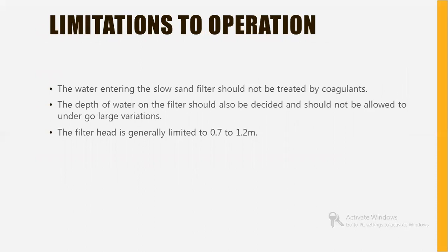Limitations of operation. The water entering the slow sand filter should not be treated by coagulants. The depth of water on the filter should also be decided and should not be allowed to undergo large variations. The filter head is generally limited to 0.7 to 1.2 m.